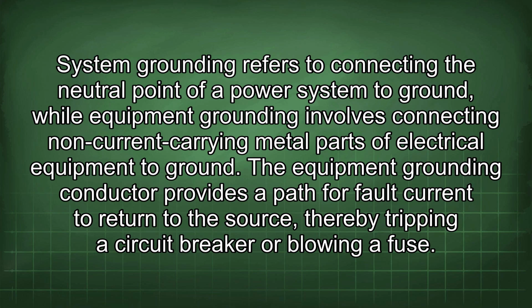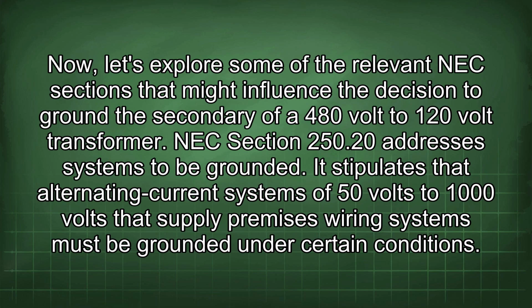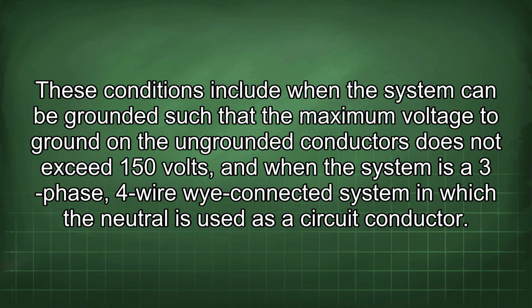or blowing a fuse. Now, let's explore some of the relevant NEC sections that might influence the decision to ground the secondary of a 480-volt to 120-volt transformer. NEC Section 250.20 addresses systems to be grounded. It stipulates that alternating current systems of 50 volts to 1000 volts that supply premises wiring systems must be grounded under certain conditions. These conditions include when the system can be grounded such that the maximum voltage to ground on the ungrounded conductors does not exceed 150 volts, and when the system is a three-phase, four-wire Y-connected system in which the neutral is used as a circuit conductor.